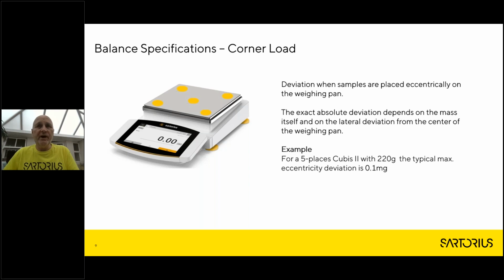So for example, on a 5 decimal place Cubis 2 balance with a 220 gram capacity, a typical maximum eccentricity deviation should be 0.1 milligram. So we want this to be absolutely as small as possible. Linear error can be adjusted at the factory by the manufacturer to be as small as we can make it.